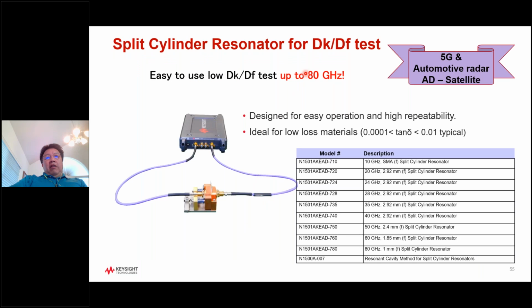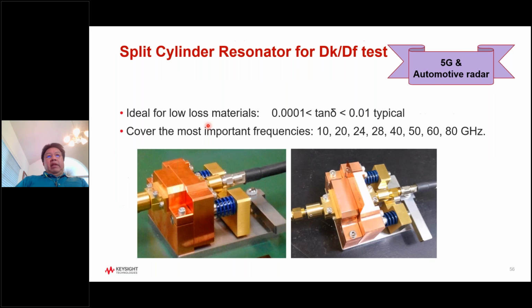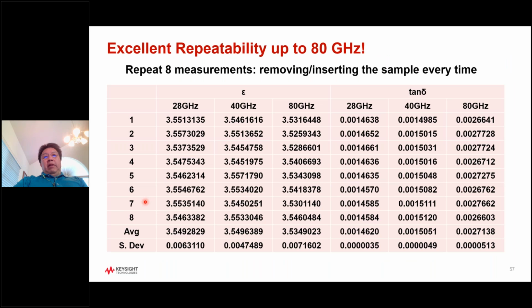Now the SCR, high frequency. In this case, I'm showing you with the USB VNA. Of course, with a USB VNA, you need a PC to run the software. The measurement is simple: close, open, put the sample in, so you can measure easily. For measurement accuracy and repeatability, you can see the standard deviation and the average. You can see all these numbers at different frequencies, all really tightly repeatable.